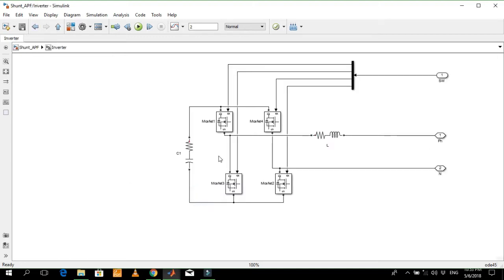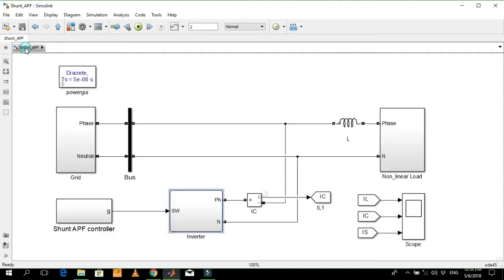The active power filter is just a bi-directional converter. In one direction it operates as a rectifier to charge the capacitor, while in the other direction it operates as an inverter to generate the required harmonics. This is the controller block which properly controls the active power filter to generate the required harmonics. In this way the harmonics are eliminated and the grid current is freed from the harmonics.